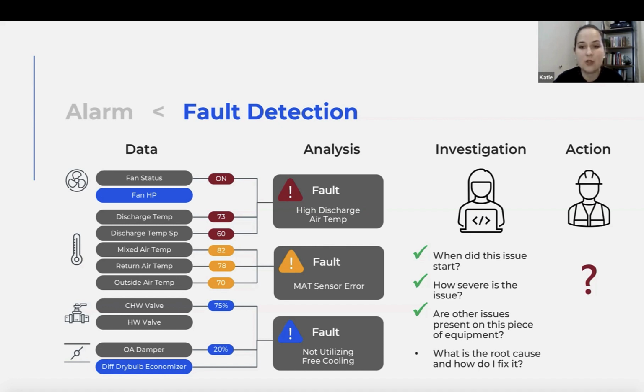So that would come to the top for you. You know if there are other issues present on this piece of equipment. So, I see a high discharge air temp, but I also see a mixed air temp sensor fault, and that I'm not utilizing free cooling. So you're putting those pieces together. You have a little bit more information, but you still need to do a little bit of investigation before you take action when you get to the root cause.